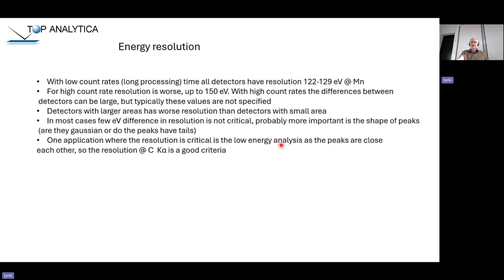If we think about the quantitative point of view, maybe the more important thing is the shape of the peaks, because very often peaks are overlapping and we have to make this deconvolution of the peaks, and then the shape of the peaks is very important. However, the application where the resolution is critical is the low energy analysis, because in that spectrum area the peaks are very close to each other, and typically the manufacturers are specifying the carbon peak resolution, and that is much more important than the resolution at manganese K alpha.